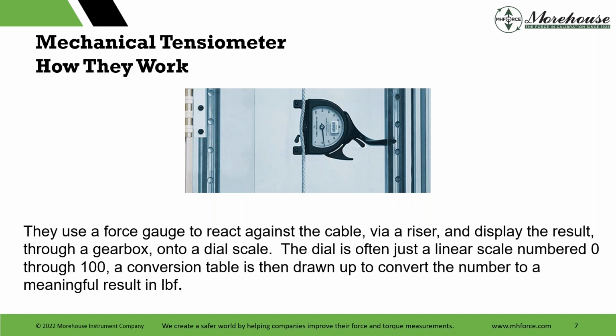But what do they do? They use a force gauge to react against the cable. There's typically a riser. This riser is shown in here. Specifications for the different risers are typically included with the tensiometer, depending if you need a different riser for different cable size. And then the dial on these is often just a linear scale, 0 through 100, really coarse resolution. We get into that discussion. Look, if these analog ones were good, they would repeat perfectly, and then all we have is the resolution that separates us between the different operators in this room. So resolution becomes pretty important when you have super coarse resolution. And then typically there's a conversion or a little chart that's drawn up to convert the number to a meaningful result in pounds force.